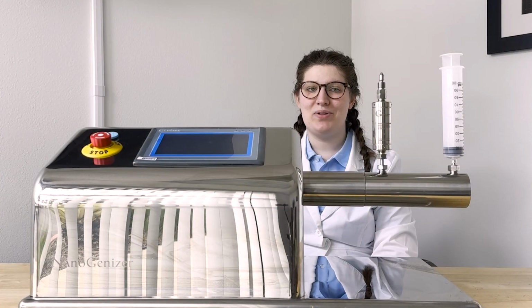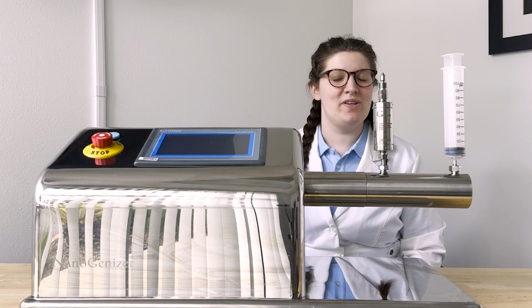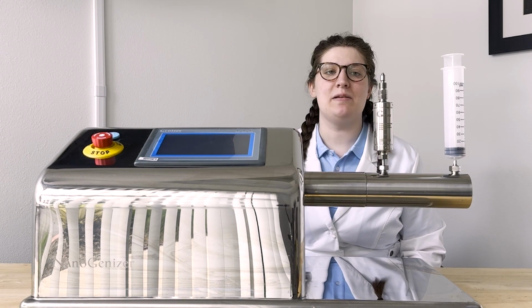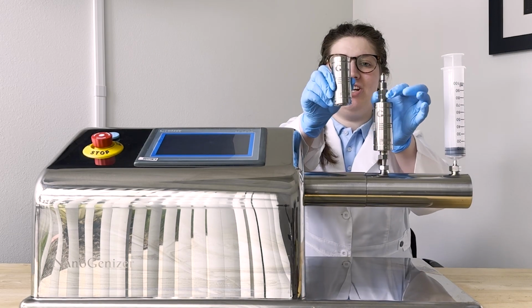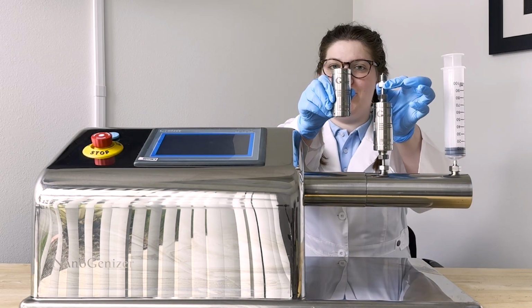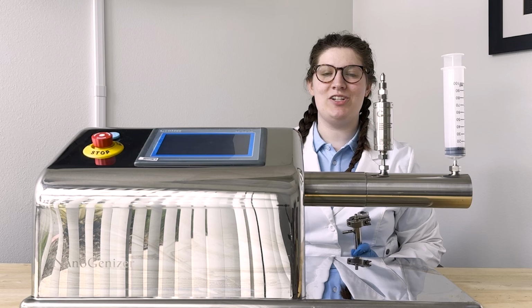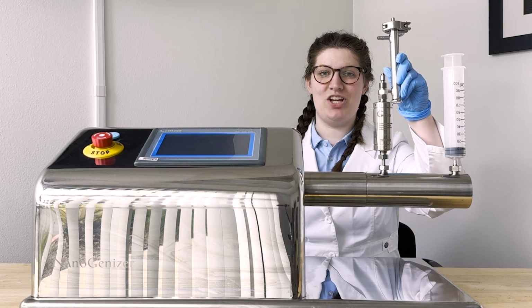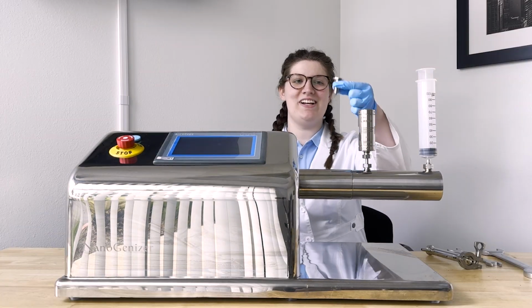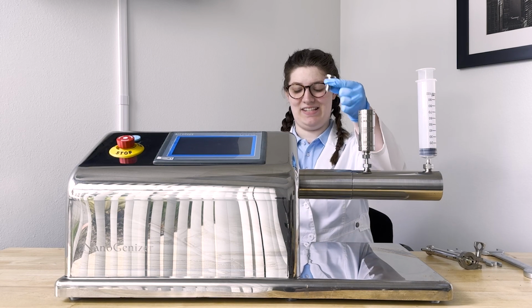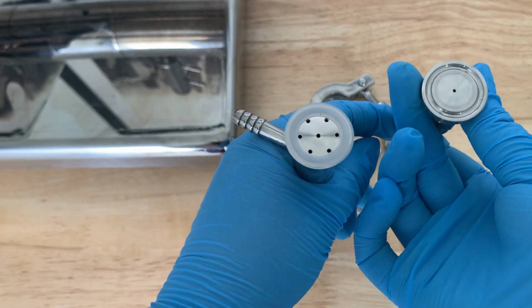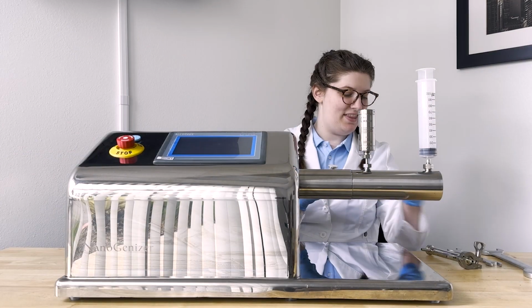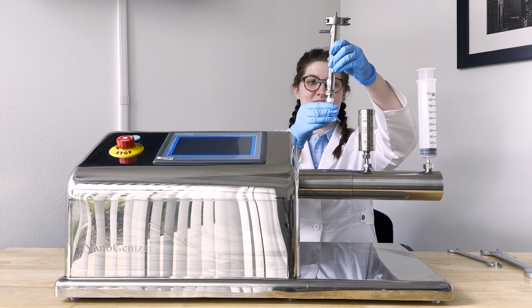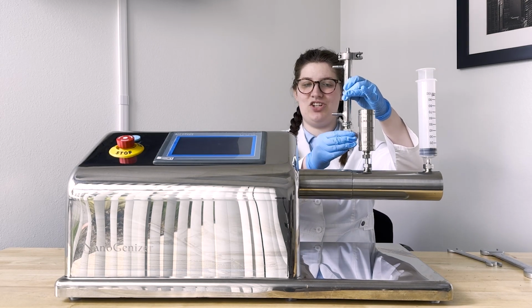The next step will vary based on your setup. The diamond interaction chamber with the double-sided high-pressure nipple assembly can be used to attach an additional interaction chamber. Another option is to set up for additional cooling with the heat exchanger. The heat exchanger will have an inlet valve that looks like this, with the seal placed there. Then, these connect to form the line of the heat exchanger.